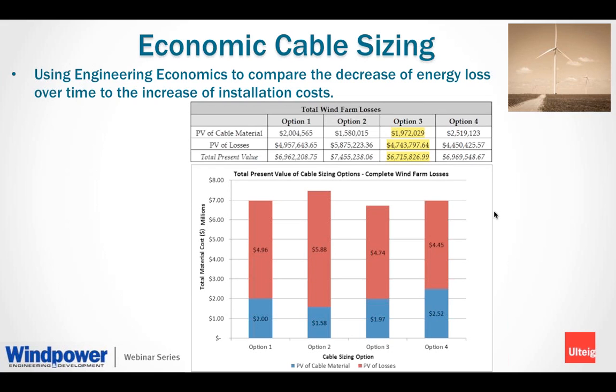We typically would like to receive a lifespan of the wind farm, a percentage rate of return, and also the cost of the power that they're going to be selling it at. And then we compare this to the cost of the cable, or the installation cost of these cables. So this was one good way of showing how you can decrease energy loss but still increase the installation costs, and over time it's actually a cheaper option.